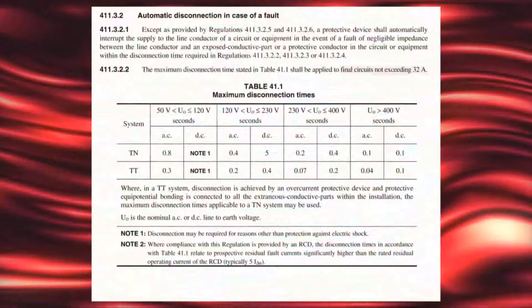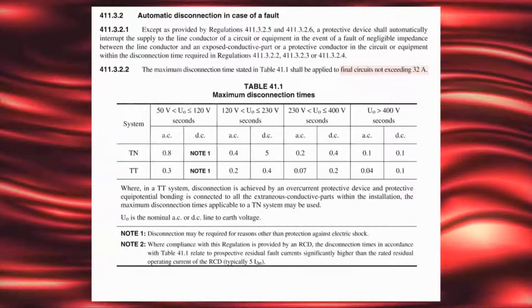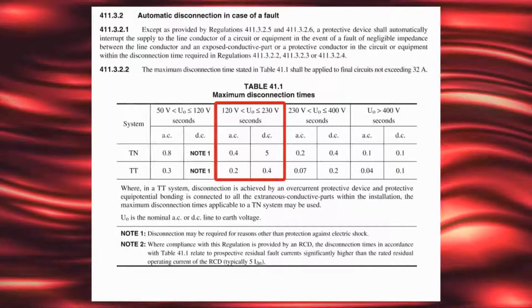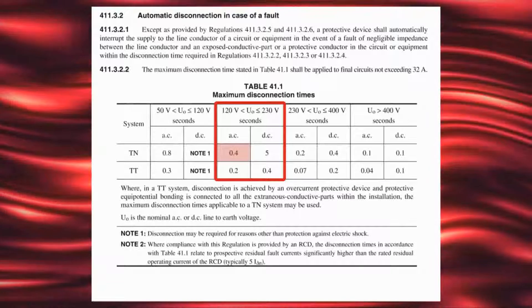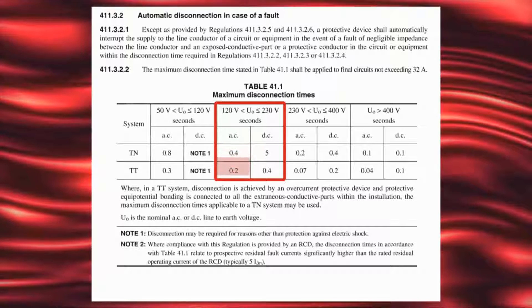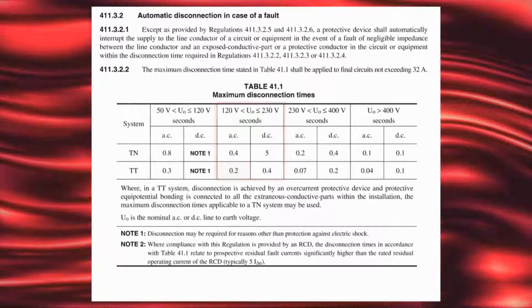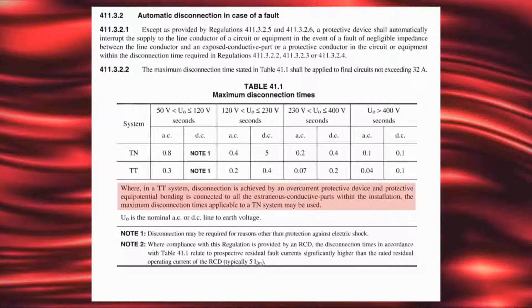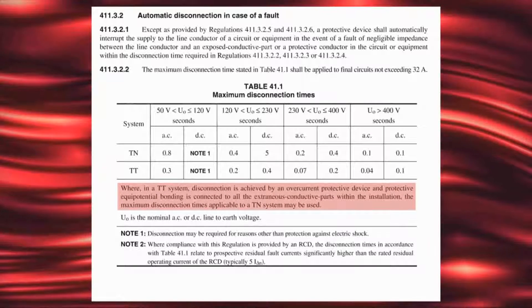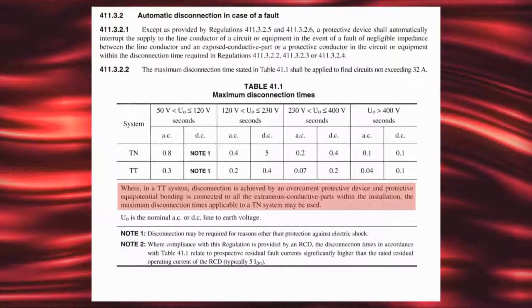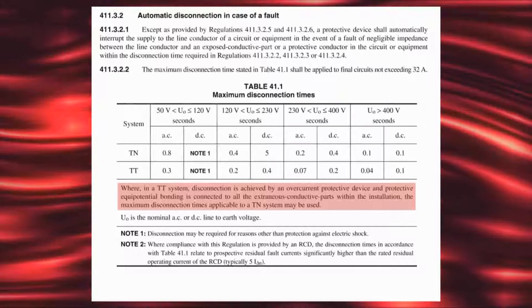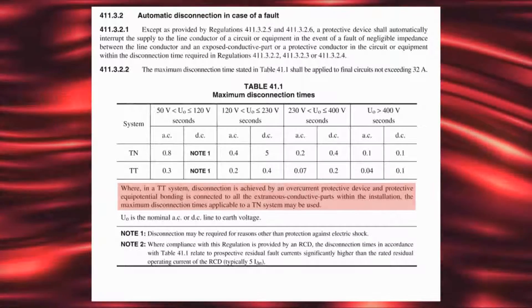The wiring regulations provide maximum disconnection times for all circuit types. This table covers final circuits not exceeding 32 amps. For 230 volt supplies, the protective device must disconnect the supply to the line conductor within 0.4 seconds on a TN system and 0.2 seconds on a TT system. However, there is a note below which does allow the same disconnection time as a TN system where disconnection is achieved by an overcurrent device and protective equipotential bonding is connected to all extraneous conductive parts in the installation.